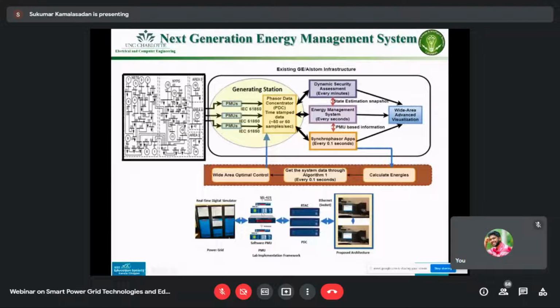So we can use relays to collect power phasor data at different points, and on the hardware side we can also get it through software. One main simulator we use in the lab for educational purposes is the real-time simulator, where you connect the hardware part and collect all that information into a central hub, also called the phasor data concentrator hub, which is also provided by a company like SEL.